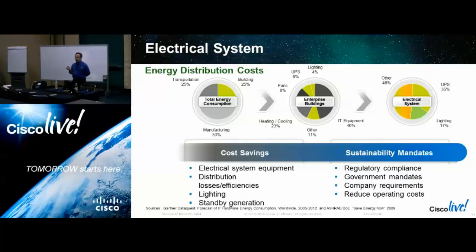The nice thing about zoning for high density rather than spread density is that you can then apply other technologies to that high density zone and extend the life and the utility of the existing systems in the data hall, cooling in particular. Because inside these specialized enclosures we touched on earlier, you can then apply stuff like in-row cooling.